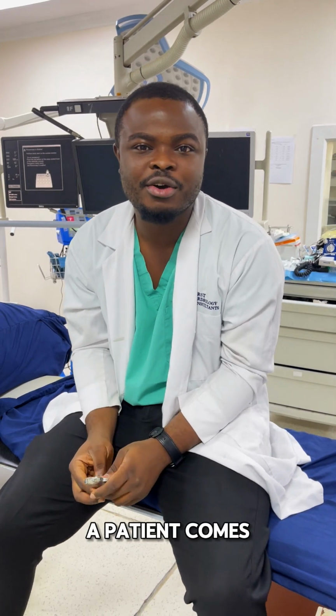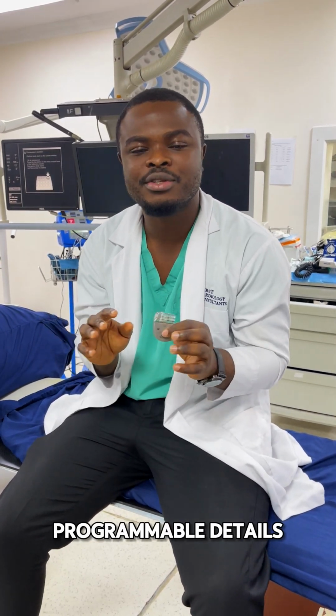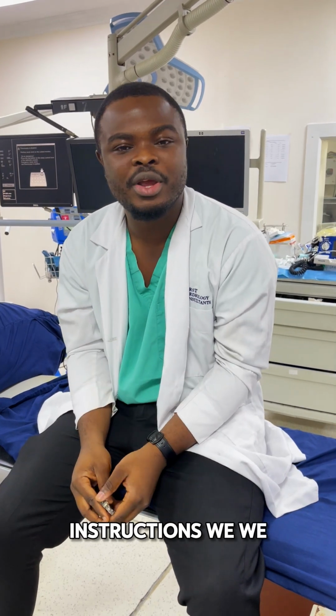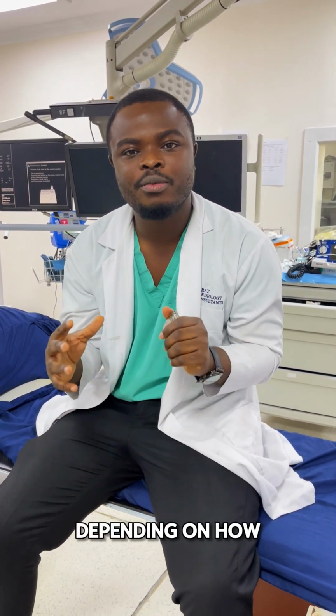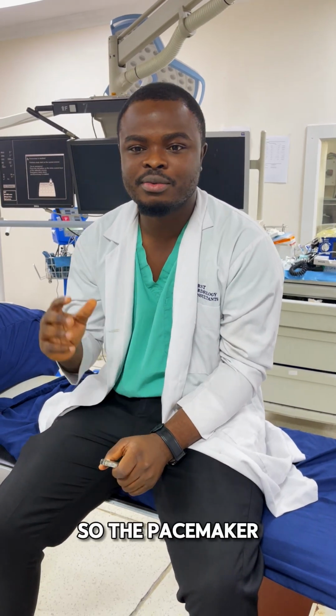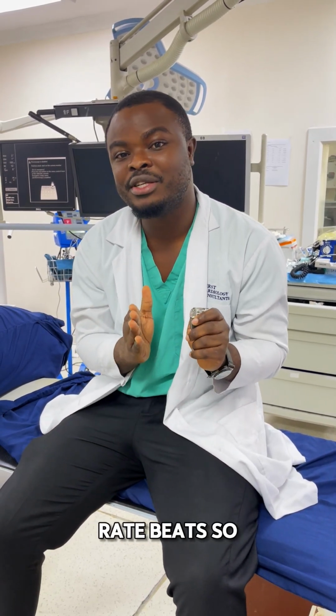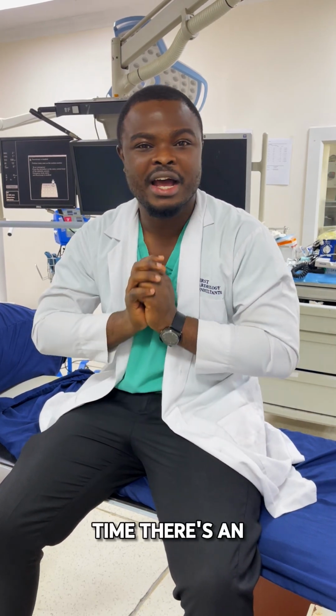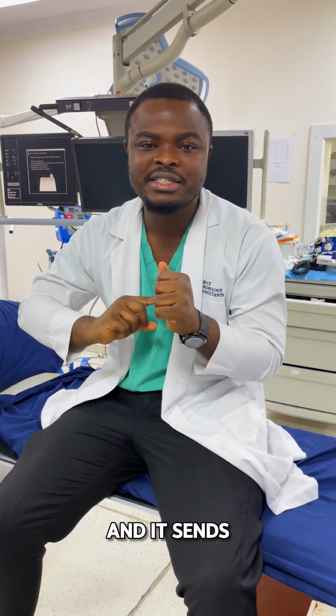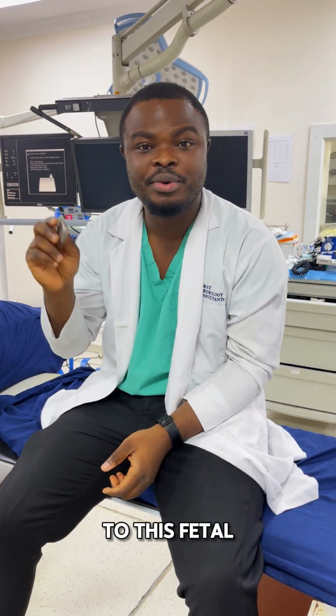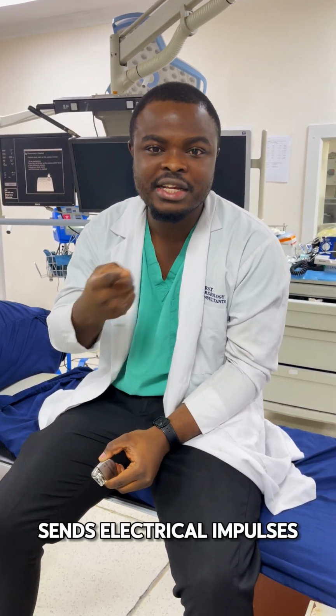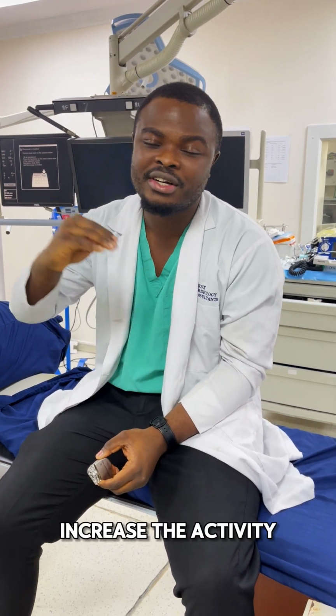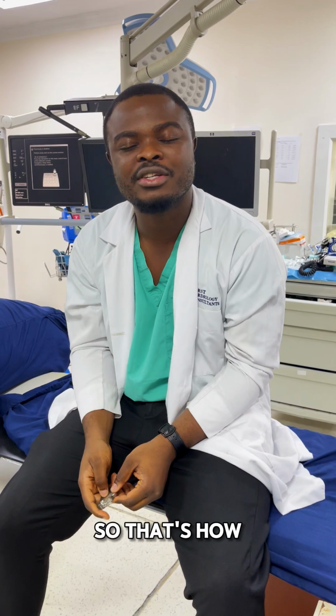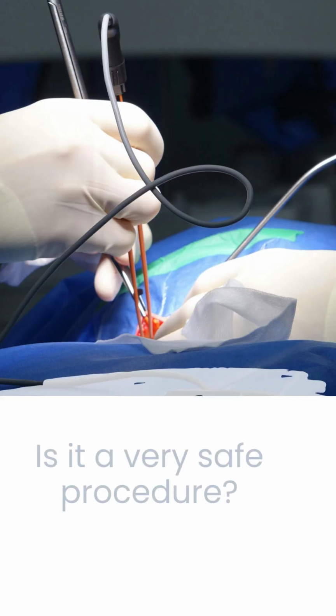So normally when the patient comes in, there are certain programmable details. We set up instructions in the pacemaker. We program a base rate of 50 beats per minute or 60 beats per minute, depending on what will be suitable for the patient. So the pacemaker senses anytime the heart beats so slowly, or anytime there's an abnormal heart rhythm, and it sends electrical impulses back to the heart muscles to increase the heart rate or to correct the anomaly. So that's how the pacemaker basically works.